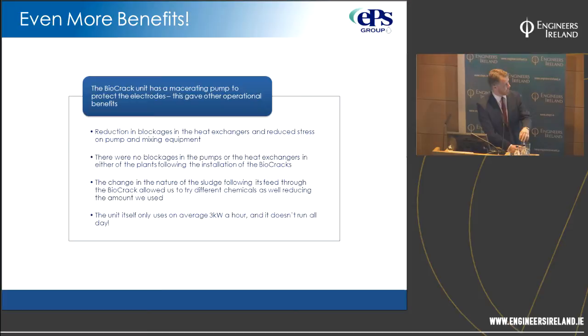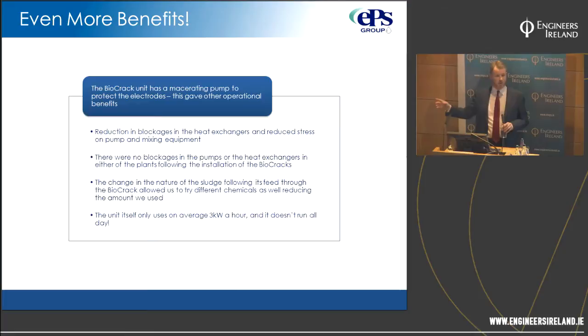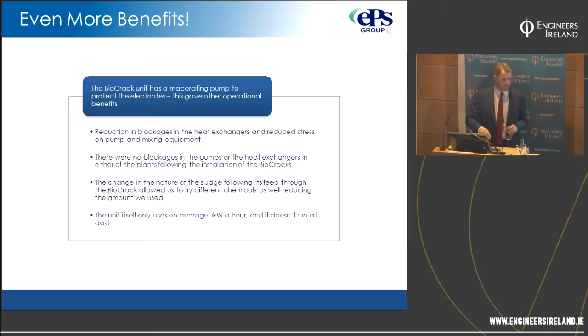The macerating pump is there to protect the electrodes, but as I said, the heat transfer and blockage prevention make it essentially maintenance-proof. Because the macerator does the maintenance for you, very little additional maintenance is required. The average energy consumption is 3 kWh — including the pump and macerator — and since it replaces a recirculation pump that would be doing the same flow anyway, the electrodes themselves at 35 watts apiece are the only real parasitic load.